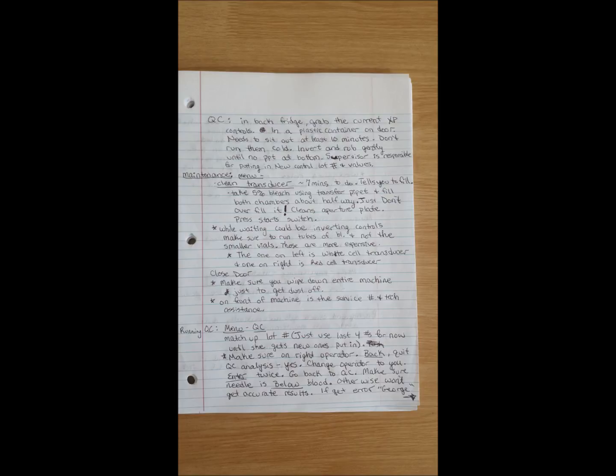Okay. So there's going to be a software screen we're going to get to momentarily. This is clean the transducers. That's this, and then that little cup down there, right? So we're going to take our 5% bleach, take a transfer pipette, and put the bleach in, when it tells us, into here. You want to make sure you don't overfill this. Okay, so you want to make sure it doesn't overflow.